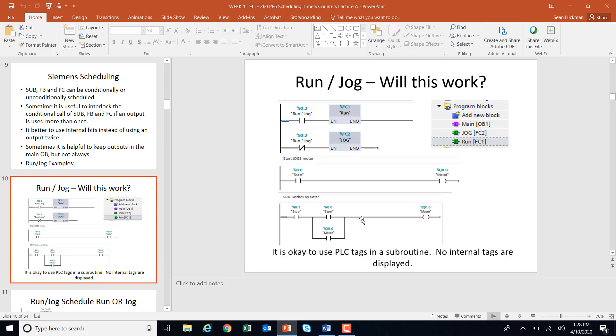Will this work? No — there's a problem. If I hit start and get the motor running, then I click the jog button, the run subroutine gets unscheduled and the jog gets scheduled. The motor will not be on. But the problem is that if these were function blocks, the run bit would still show memory inside. As soon as I click back into run, the subroutine gets scheduled again and the motor would automatically start up. So this actually won't work. The retentive nature of subroutines when you're conditionally scheduling things can be a big problem.